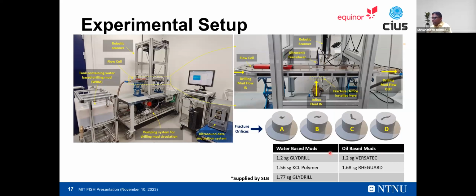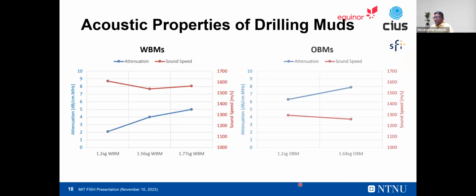These are used most commonly, and it also covers the full spectrum of densities, or mud weights as they call them, in both cases, stretching from the lighter 1.2 specific gravity muds to the heavier 1.7, 1.8 specific gravity. Just to let people who don't know about drilling fluids, these are extremely attenuative fluids and very bad to work with for ultrasound. We'll see that in these slides. So when you look at the acoustic properties, for example the sound speed of the drilling muds, the red curves here split across the water-based and the oil-based mud. But what's interesting to see is the attenuation. And this is the attenuation per centimeter at 1 megahertz.